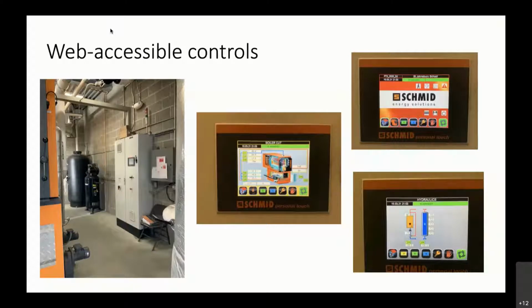When we run into trouble, the manufacturer is from Switzerland, and they will come in fact, help us with tuning when we needed to decipher why we wouldn't get full output in the beginning. They were actually able to test and see that the feed screw from the stoker motor was just not transporting enough fuel in, and so really by electronic function, they were able to discern what was wrong with it, and it's quite helpful when you have long distances in between. Also, now it's tuned in through their BMS, and so their local plant manager can quietly see all the boiler functions and the temperatures and see if that is in good operation.